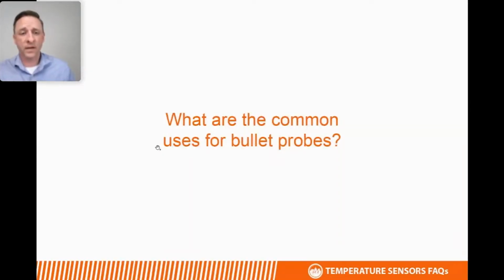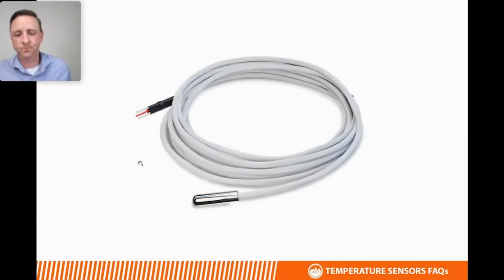Standard bullet probes are kind of the jack of all trades of temperature sensors. That's a common question: what are the uses? What do you use these for? The options really are limitless. You can drop them into a thermal well. You can strap it to the outside of a pipe. People will hang them inside of an existing room sensor enclosure. So say there's an existing thermostat on the wall and you're replacing it with a DDC system. You can put the bullet probe inside of that housing and just wire that back to your DDC system. They can be tied to heating and cooling coils. So there's really no limit to the number of options or where these can be used.